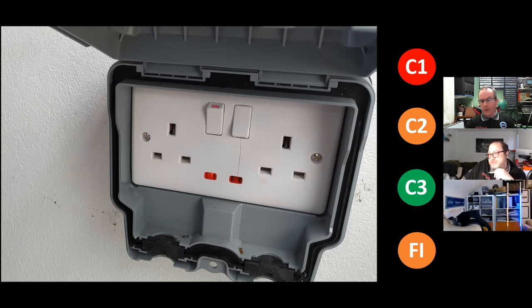It was on the outside wall exposed to rain, and the cover was open when I found it. So what did you code it? What does everyone else think? I think everybody's going C3. Sean's being over the top as usual, drama queen, C2ing it. Well, obviously, Sean, in this case, John just said the cover was up. So we've got to then say, well, is that adequate IP protection if the cover is always up?